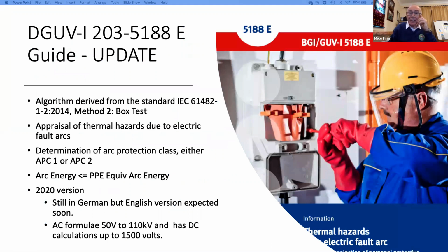Next is the DGUV guide, which is based upon an algorithm theoretically derived from a box test method for evaluating PPE in accordance with the IEC standard 61482-1-2. The one that's used predominantly for creating an ATPV, as I suggested earlier, is what's called open arc testing. This is the box test, and it is used predominantly in Germany, but it's a very simple test actually, similar in setup to the example that I gave at the beginning. Can you remember the two bus bars that were facing each other, 30 millimeter gap? Well, the box test is a 30 millimeter gap.